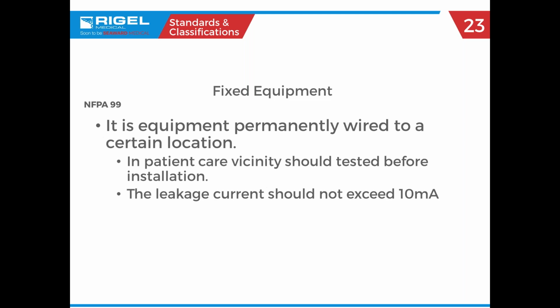So when we're looking at fixed equipment in a facility, fixed equipment is permanently hardwired directly into the facility itself. So that actually needs to be tested prior to it even being installed. This is primarily where you'll see this equipment, in the OR. And these requirements say that the leakage should not exceed 10 milliamps.